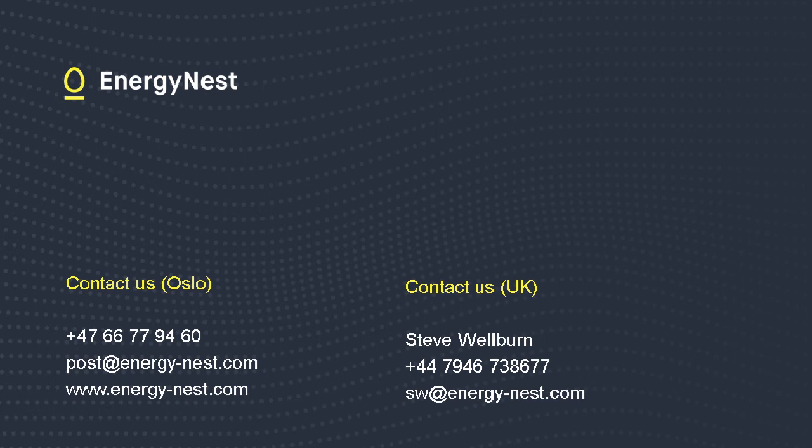Our concrete, the heatcrete, which we developed together with Heidelberg Cement, has a very low water content, let's say 6-7%. So there are additives that make it workable with such low water content. And also, as I mentioned, we do the conditioning, which is heating it above the boiling point of water, and we get the additional unbound water out of the concrete. That has an effect on the strength of the concrete. And that is, we believe, due to the vapor pressure at higher temperature that actually forces more water into the fine cement grains and makes the concrete stronger.